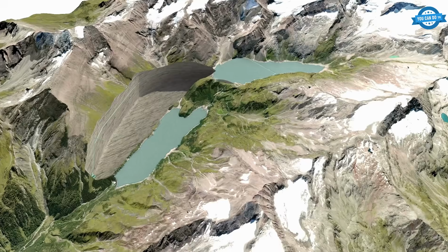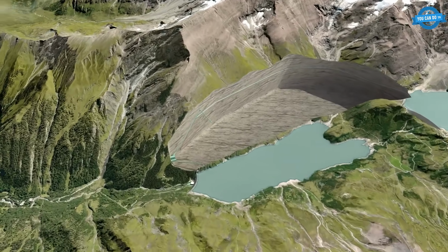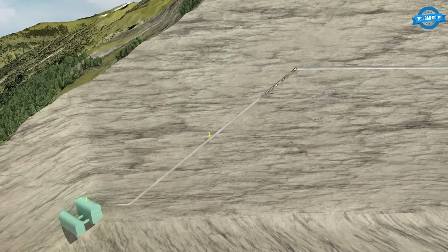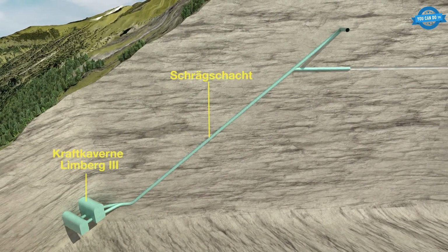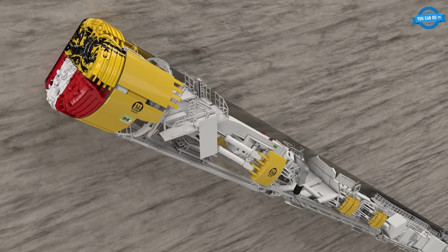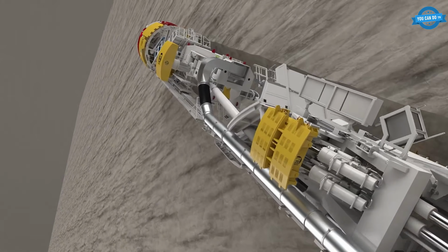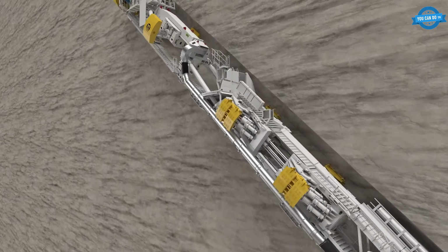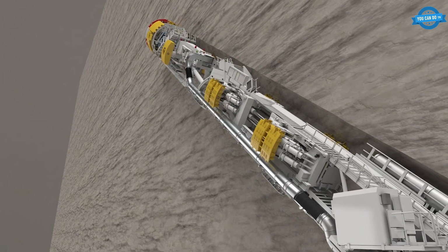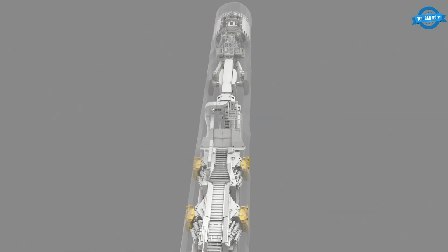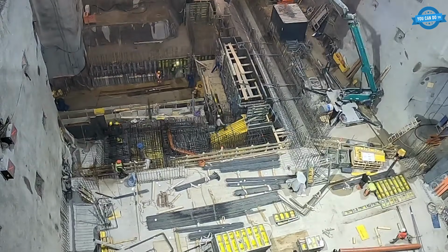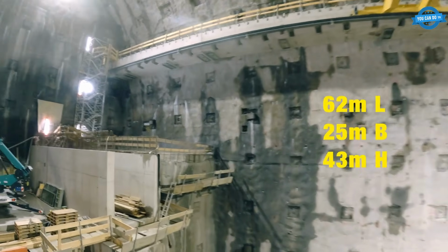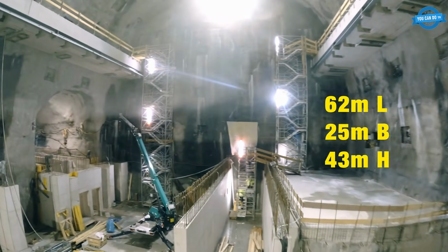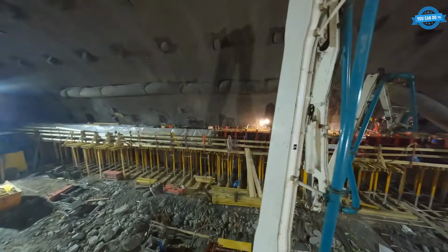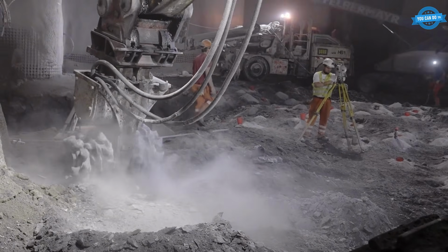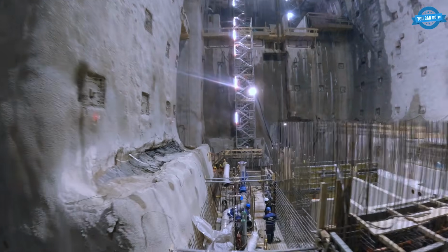The pressure shaft is a feat, 770 meters long, 5.80 meter bore diameter, climbing a gradient over 90%. A custom 105-meter, 1,000-ton boring machine cut it in 4 months. 3 bracing levels kept the machine from sliding down the slope at any operating state. The cavern reaches 62 meters long, 25 wide, 43 tall, 51,829 cubic meters of rock blasted out using 64 tons of explosives.